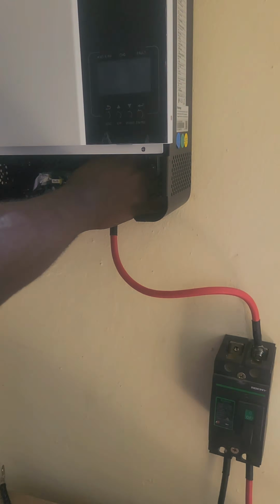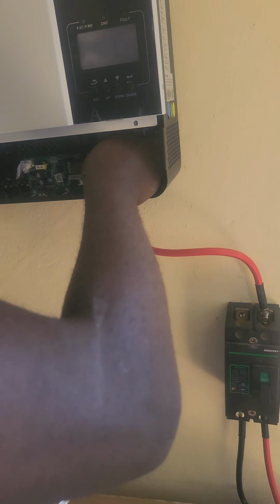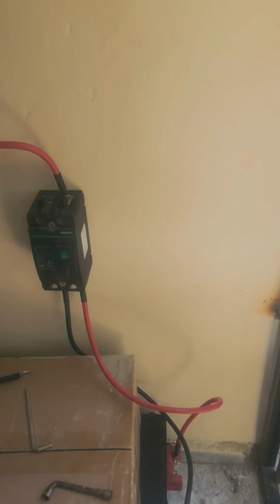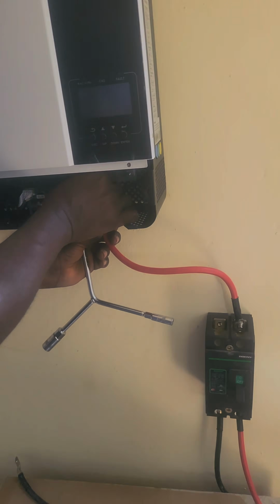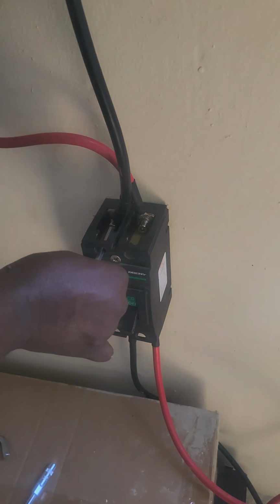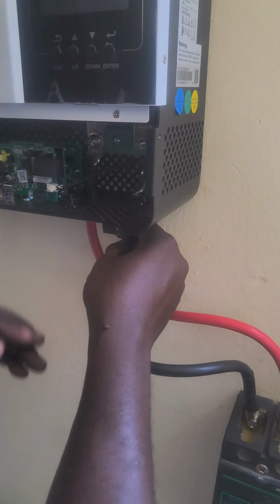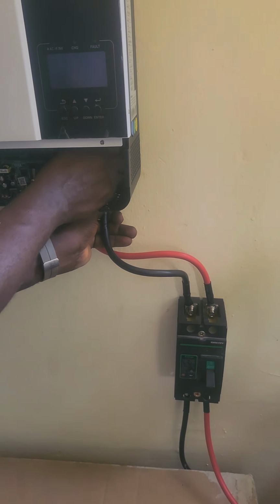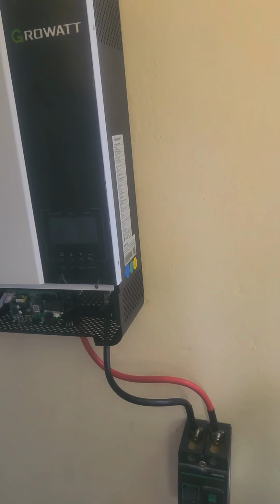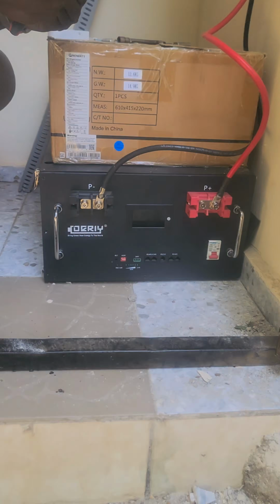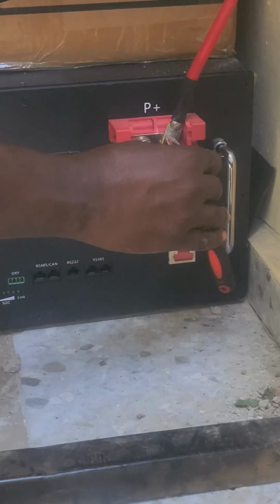I'm connecting the battery to the inverter, with the battery coming through the MCCB, connecting to the battery terminals on the inverter. This ensures you have a very safe system and protects it from things like fire, which you really don't want in your installation. Even though this is a DIY system, try as much as possible to be compliant.